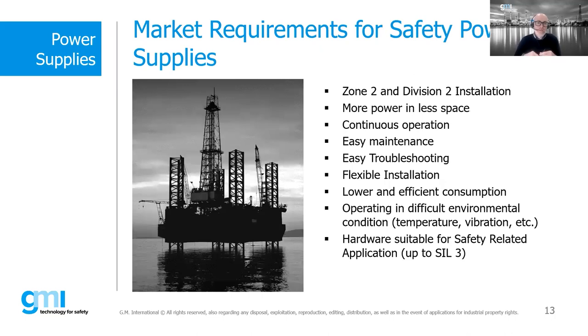But what are the most important requirements that the market asks of us for this highly reliable power system? Of course, a safety power supply has to be compliant with the IEC 61508 regulation and meet the demands of functional safety. Another key point for the market is the possibility to install the power supply system in a certified area. This allows us to install the system closer to the load, saving on cabling cost.